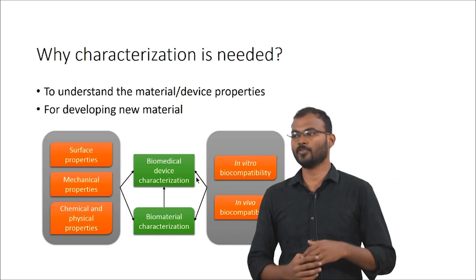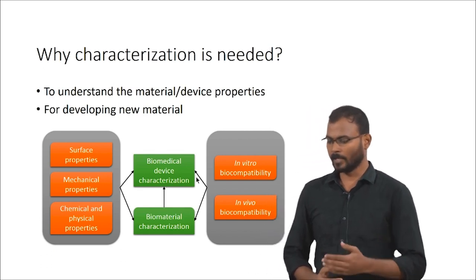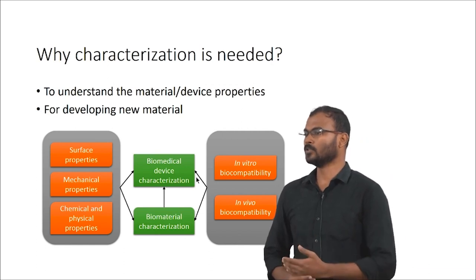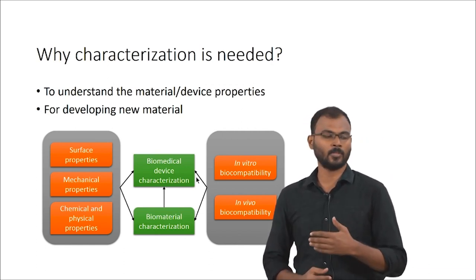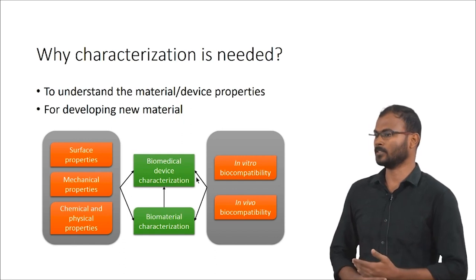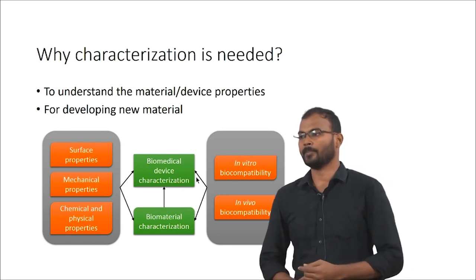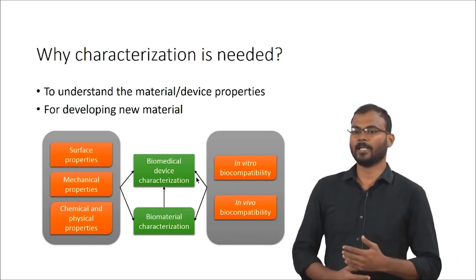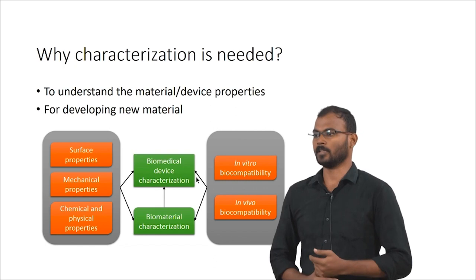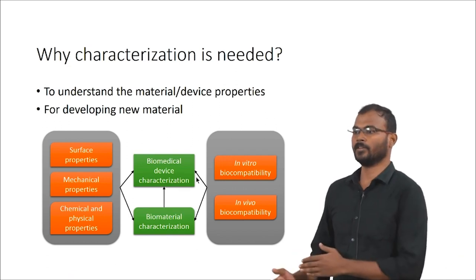Before going for clinical application, we have to previously test the material with in vitro and in vivo testings. In vitro biocompatibility involves whether a material is suitable for cell adhesion, whether there is an immunogenic response from the cells, whether there is protein adsorption, and whether blood coagulation occurs on the material surfaces. In vivo biocompatibility involves testing the material in animal models like rats, pigs, and dogs to check whether the material has the same function when introduced into a human body.